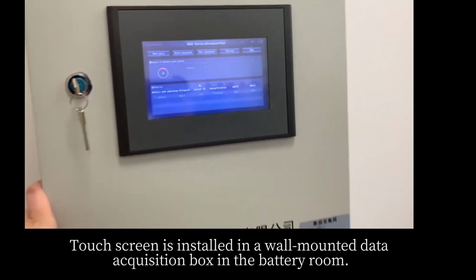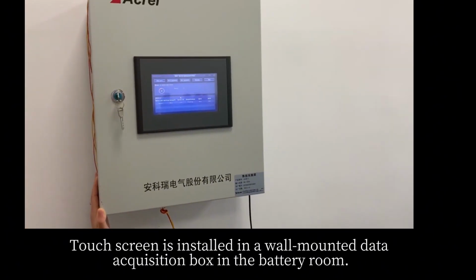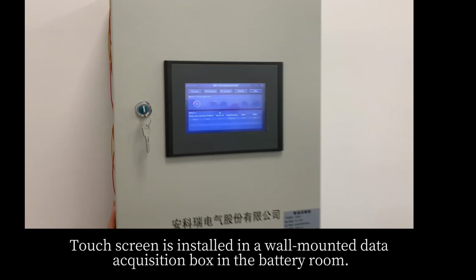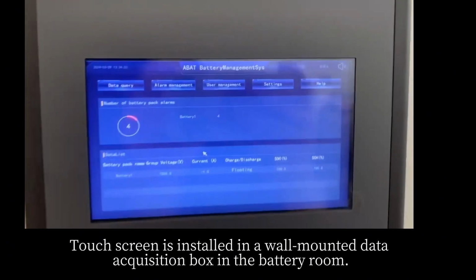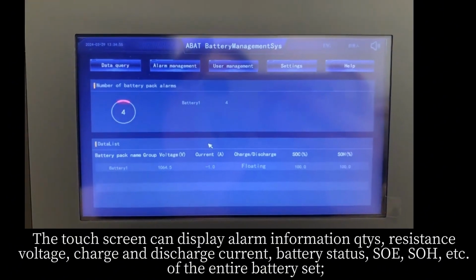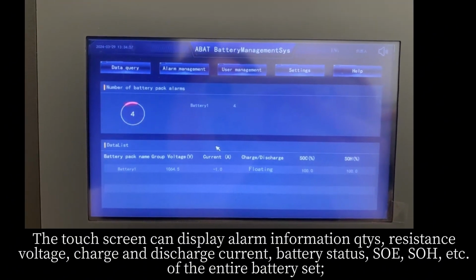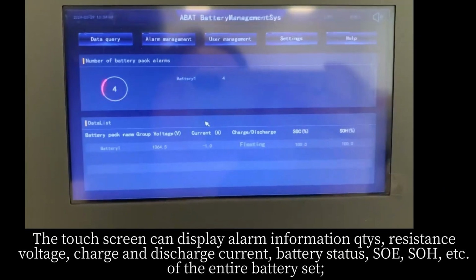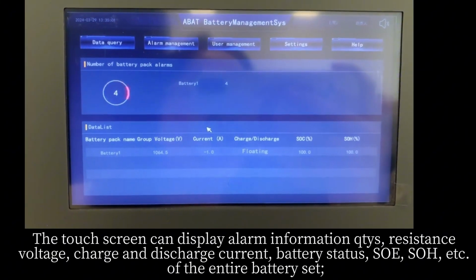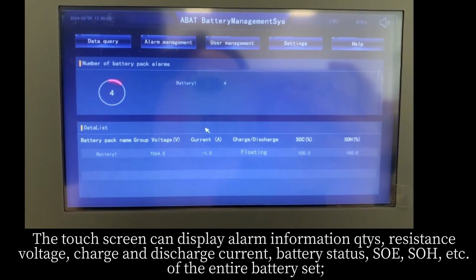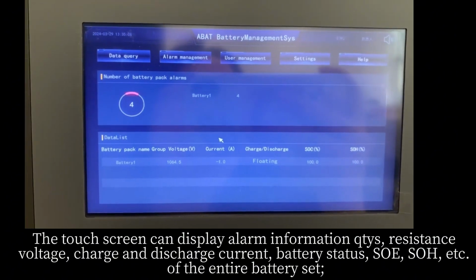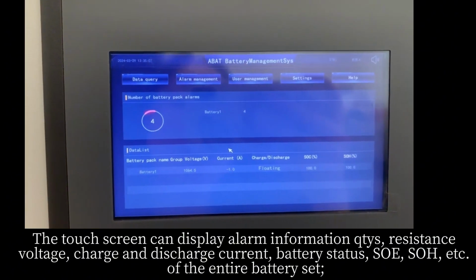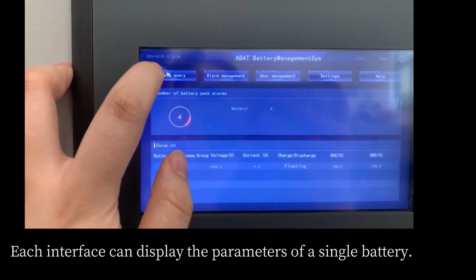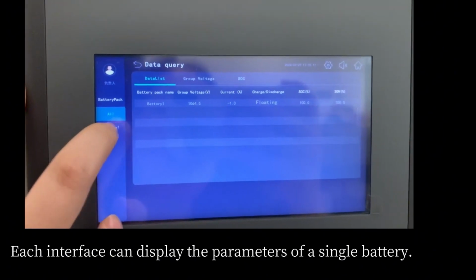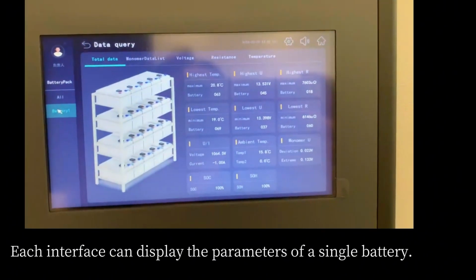The touchscreen is installed in a wall-mounted data acquisition box in the battery room. The touchscreen can display alarm information, quantities, resistance, voltage, charge and discharge current, battery status, SOE, SOH, etc. of the entire battery set. Each interface can display the parameters of a single battery.